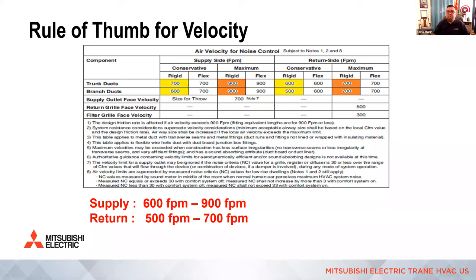All right. Karen asked me to just repeat why there's a minimum feet per minute and why it is a problem to oversize ductwork. Great question. Everybody thinks bigger is better with ductwork. Unfortunately, we're designing around your highest speed in this example. So if you can imagine, if we didn't have a minimum, what happens to the airflow when we actually turn the speed down, right? When that speed turns down because the demand turns down with a variable speed heat pump or furnace or anything really, air conditioner, then the feet per minute slow down and, like Steve said, stratification in the room, you're not going to be able to blow the air across that entire wall or floor, right? And instead of throwing, let's say, 8 feet to a ceiling from a floor register, it might only throw 4 feet and we can't mix the air in the room and you have uncomfortable spaces. And we also can't get that latent heat back to the return by not mixing the air in the space.